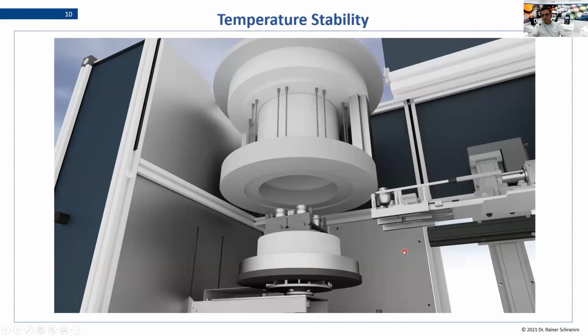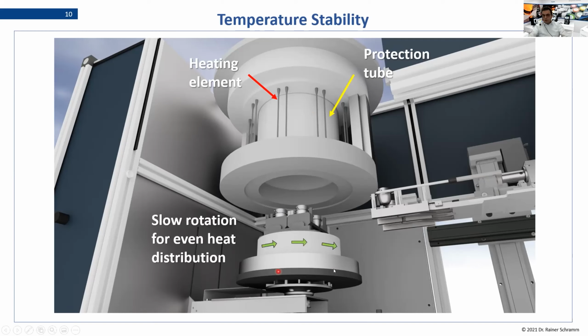But important is how this furnace is constructed. So we have our heating elements which are sitting around the furnace. We have a protection tube which protects the heating elements from the samples. Very important. So this guarantees that they last much longer than if you don't have this kind of protection. And even in maintenance, this tube can be exchanged easily so that once it is contaminated, you can replace it from time to time to keep your furnace safe and clean. The agitation is done here with the bottom, and we have either the slow agitation or the fast one.